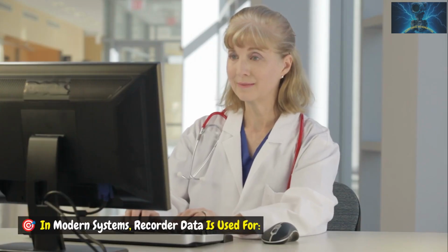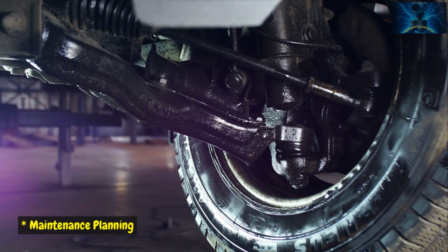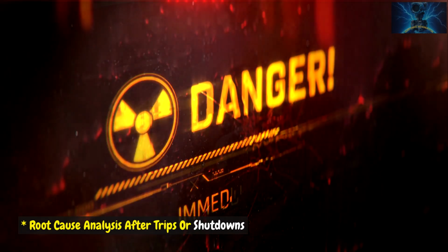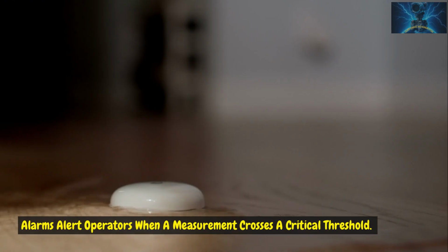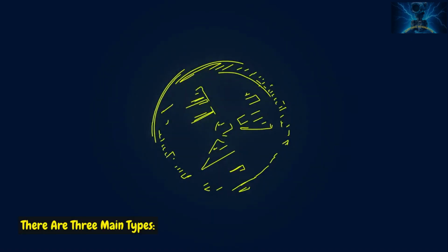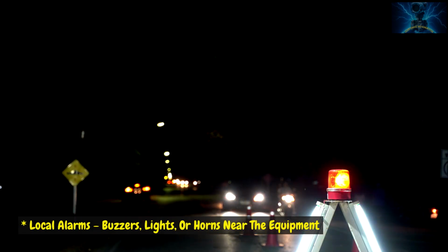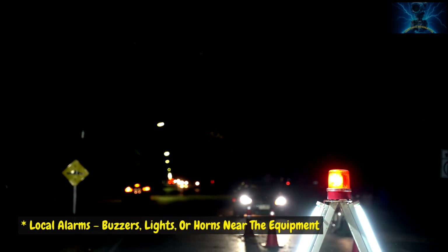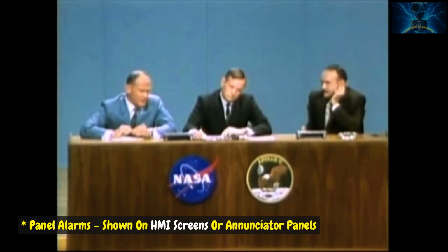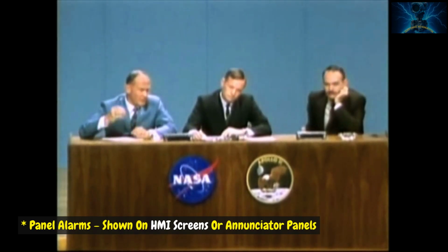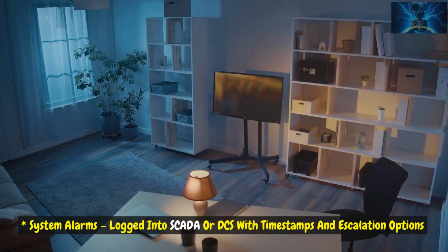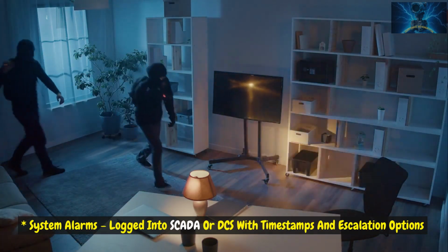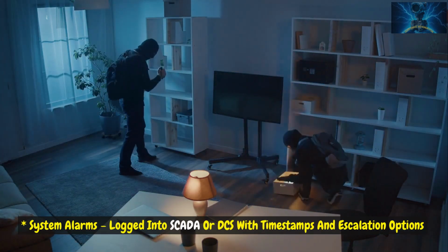In modern systems, recorder data is used for maintenance planning, energy optimization, and root cause analysis after trips or shutdowns. Alarms. Alarms alert operators when a measurement crosses a critical threshold. There are 3 main types: local alarms, buzzers, lights, or horns near the equipment; panel alarms, shown on HMI screens or annunciator panels; system alarms, logged into SCADA or DCS with timestamps and escalation options.